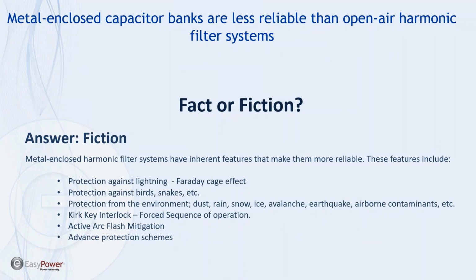All right, there's a notion that metal-enclosed capacitor banks are less reliable than open air harmonic filter systems. And again, this is not a true statement, it's fiction. The metal-enclosed solution in years past, and I'm going back maybe 25 years ago, there was some reliability concerns. This is back right when we got into the industry. Iron core reactors were overheating and failing. So there are a lot of old-time engineers out there who had experienced this issue.